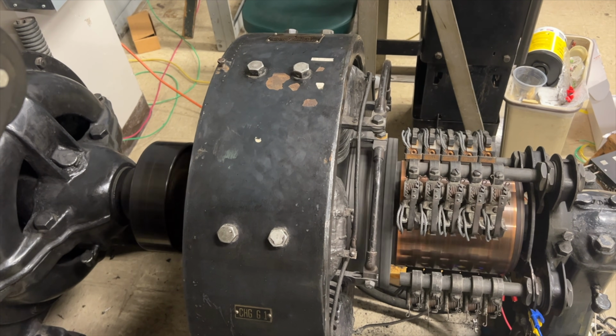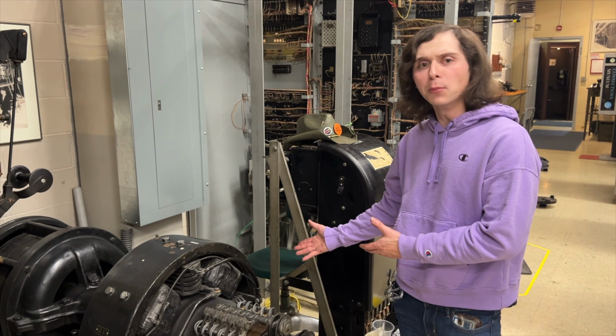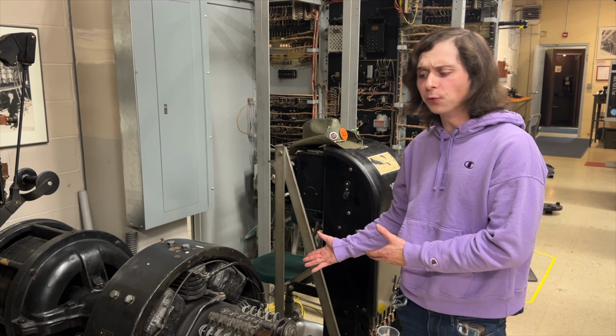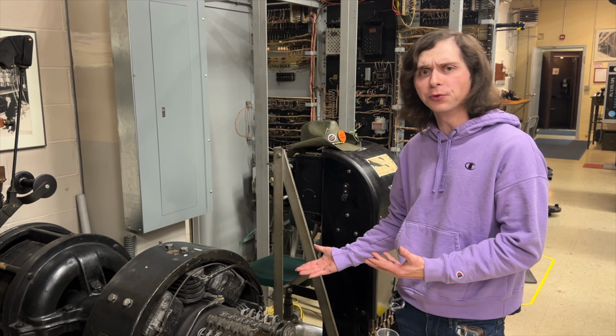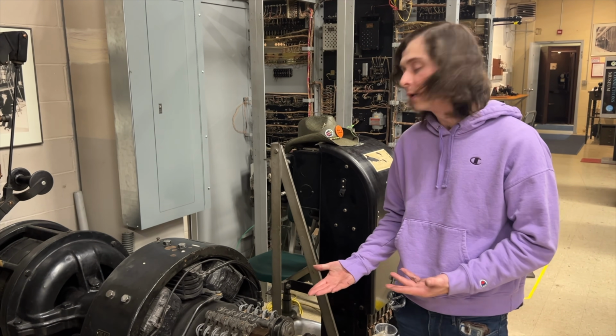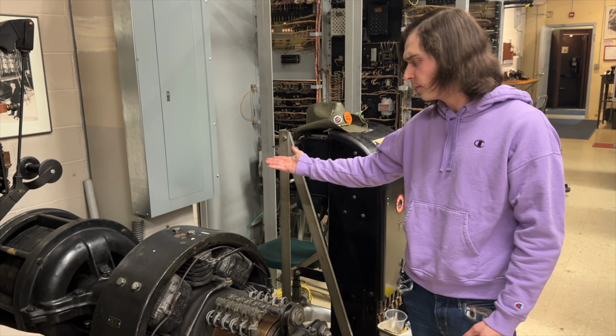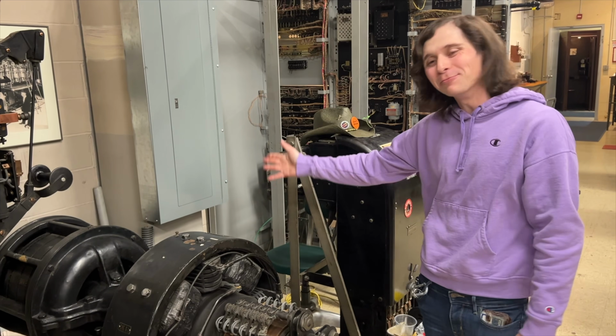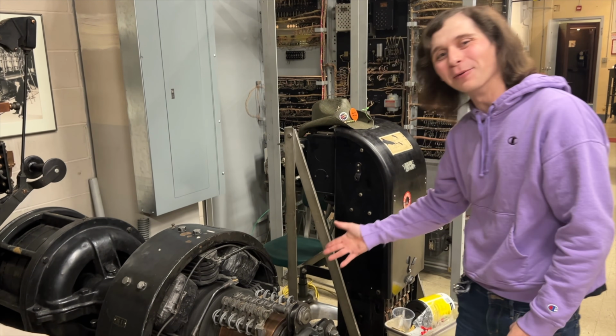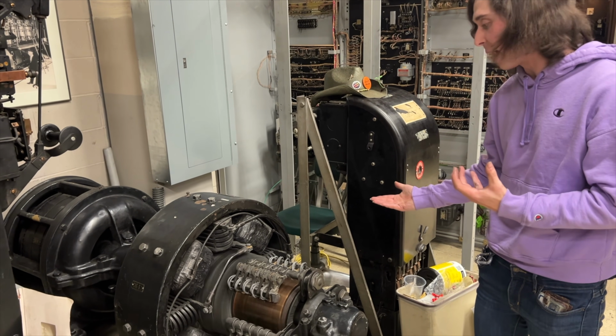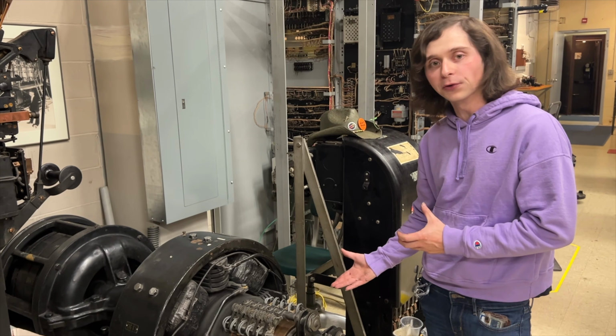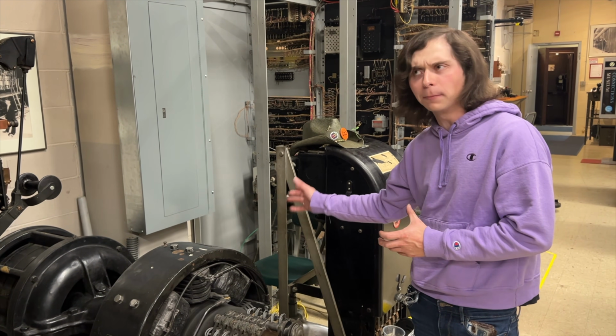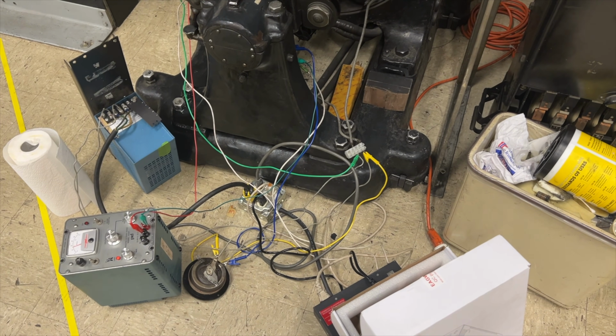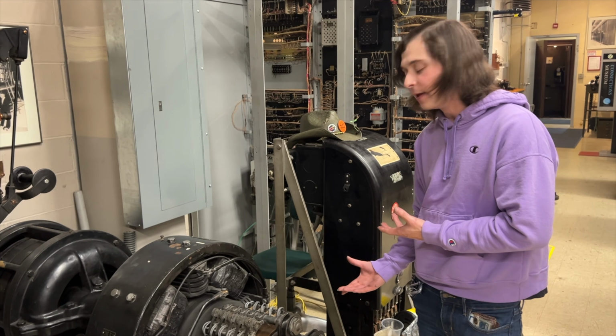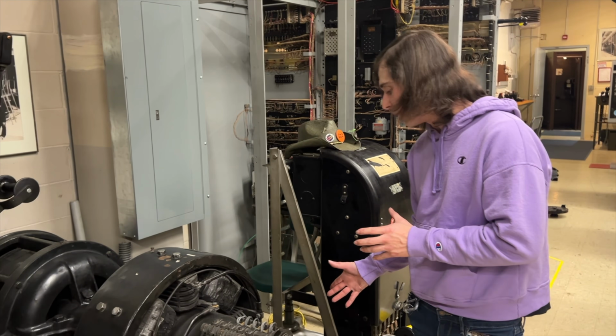Okay, so this is the newest thing we have just got working. This is a motor generator set that would originally have been used to charge the lead-acid batteries that we use for powering all of our telephone switches here. It consists of an AC generator, AC motor, and a DC generator right here to generate 48 volts for charging the batteries. Right now we have this running in reverse. So we have 48 volts applied to the field and applied to the brushes, and we're basically spinning this as a motor right now. And pretty sure it's at full speed right now, and it's kind of scary to be around.